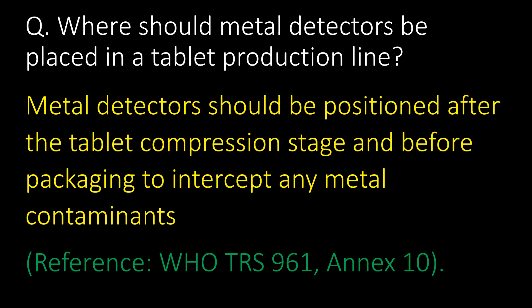Where should metal detectors be placed in a tablet production line? Metal detectors should be positioned after the tablet compression stage and before packaging to intercept any metal contaminants. Reference: WHO TRS 961, Annex 10.